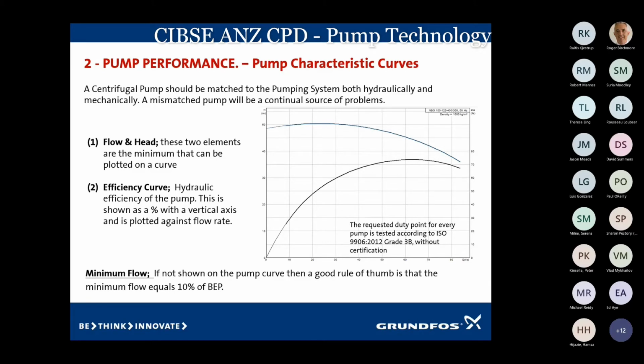The performance curve is a promise by the manufacturer that that pump will actually meet that curve, and each pump is tested to that pump curve prior to being dispatched. There is a tolerance around that curve, so as long as the guys that are assembling and testing the pump meet that tolerance, then the pump can go out. We can't get off that performance curve. If it's a fixed speed pump, we have to stay on that performance curve.